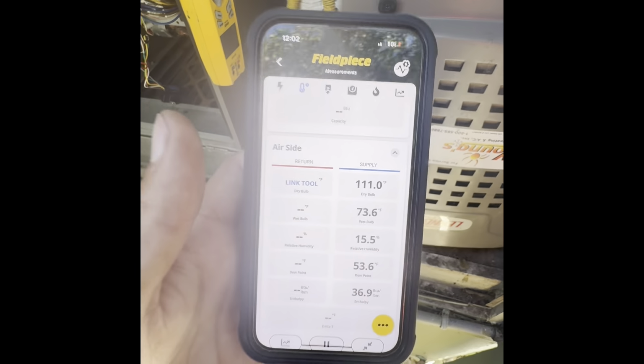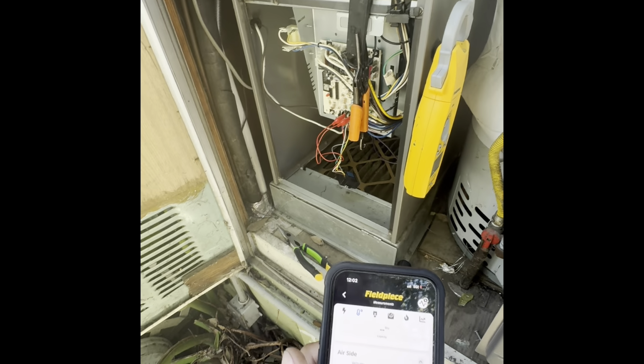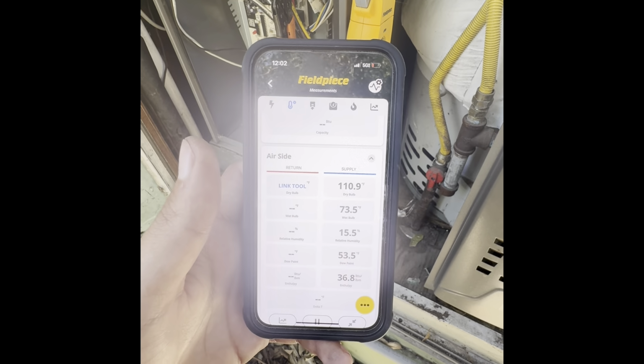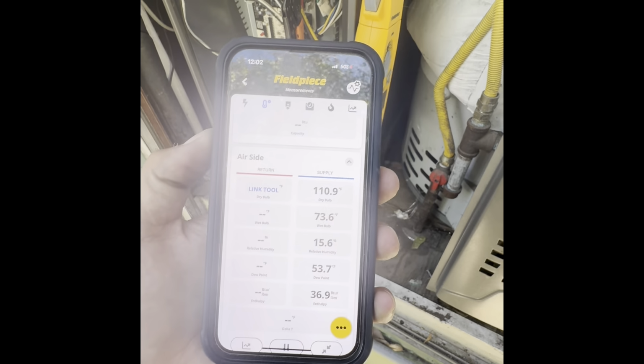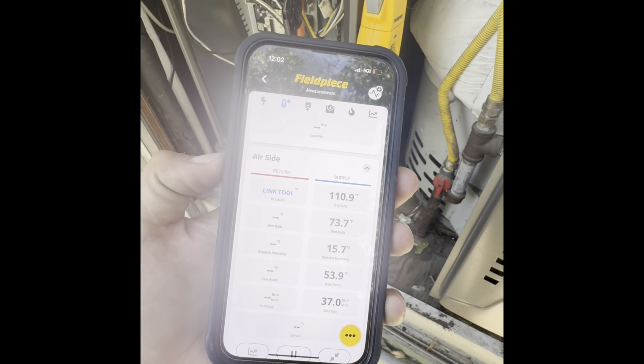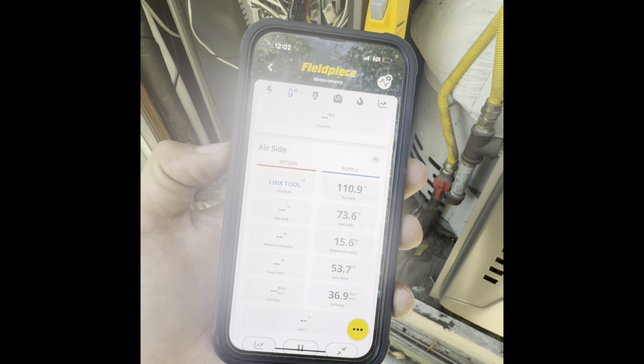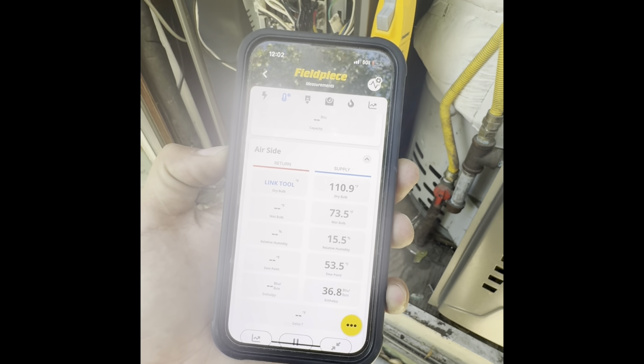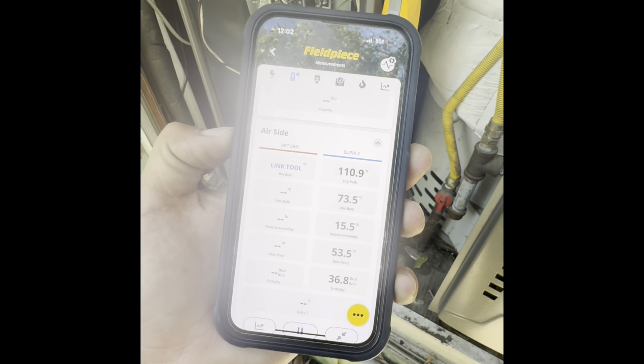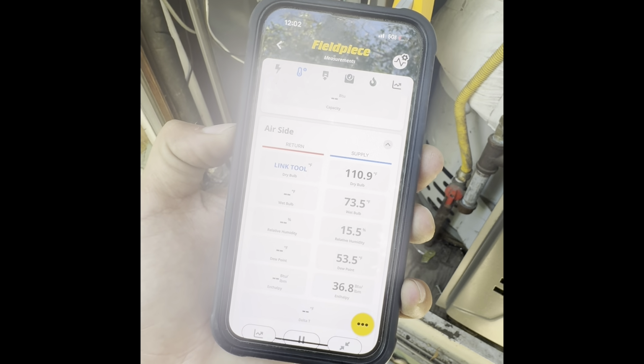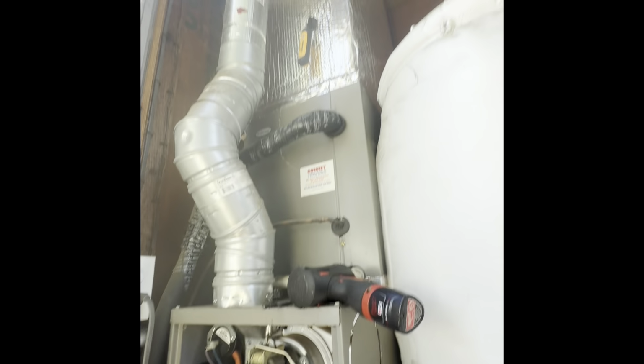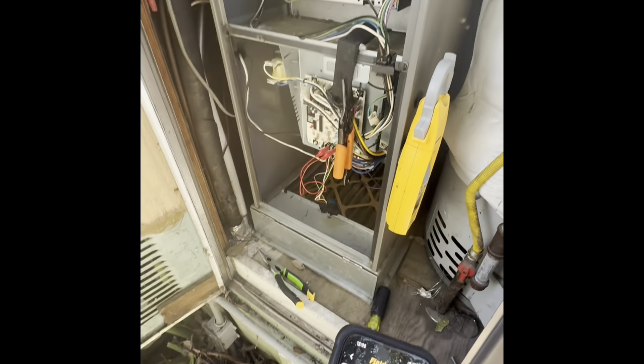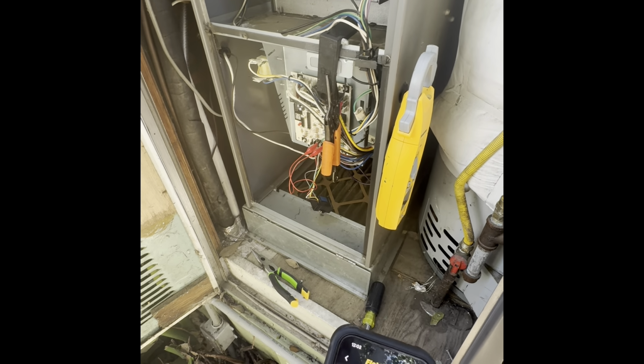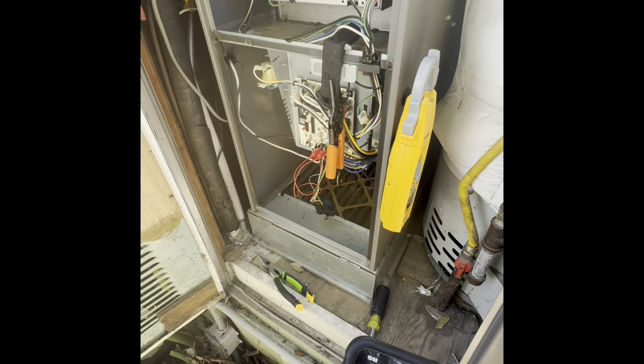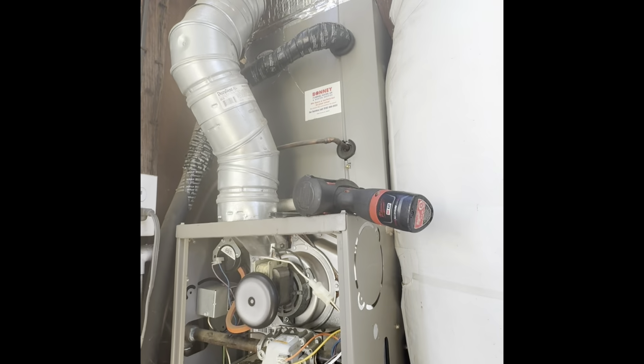Okay, so right now with the door panel off, it's 110. Seems like it's staying steady around 111 degrees Fahrenheit. I don't think it's gonna move any higher than that. So what I'm gonna do is move the sensor from up there down here to be able to compare the incoming temperature to the supply temperature.